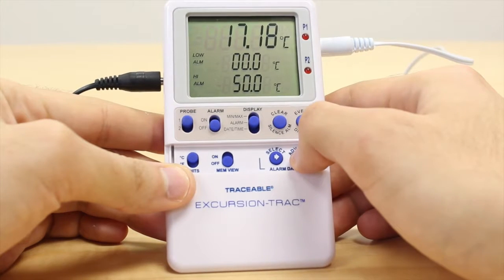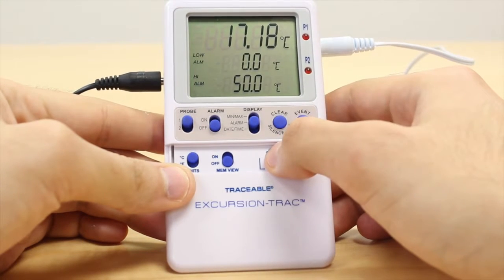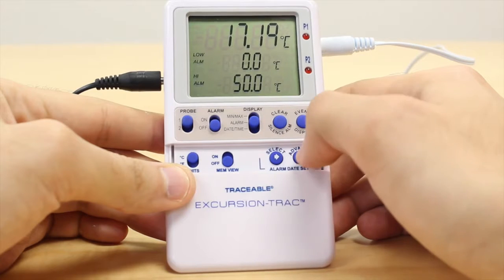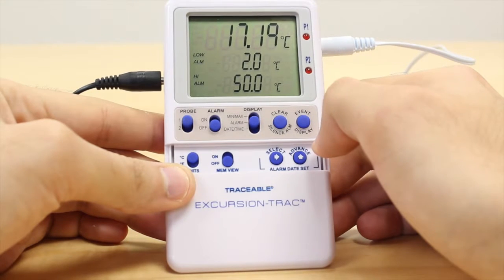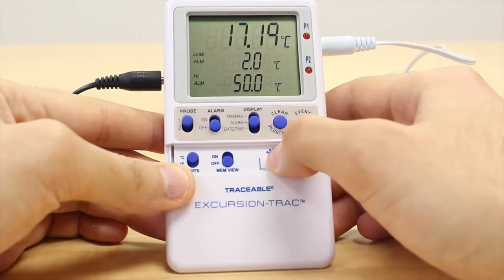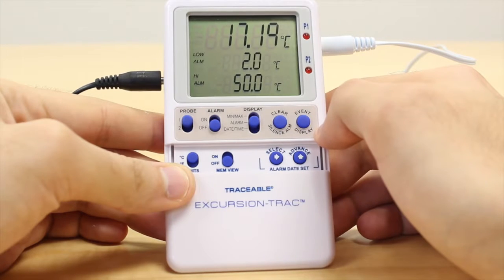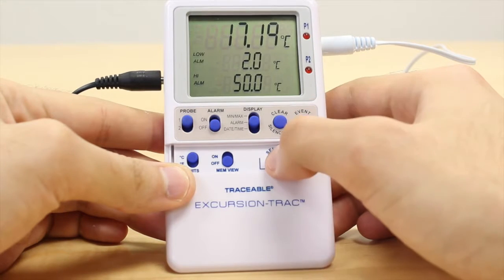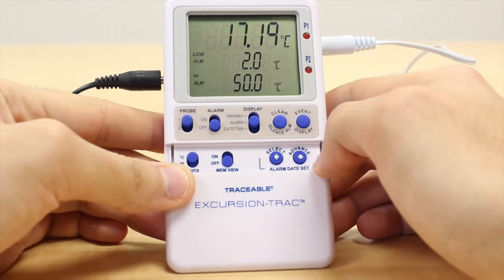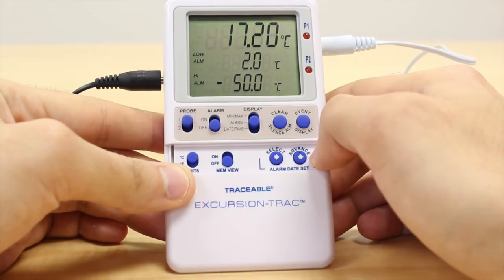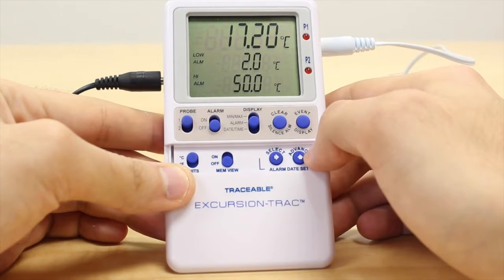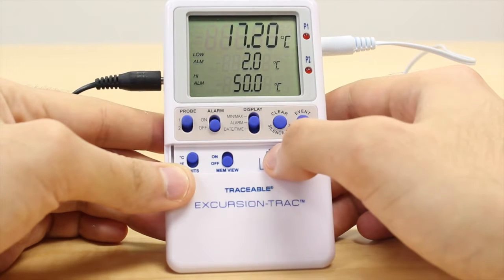Press the Select button once more to move on. Here is where I need a 2. Use the Advance button until you arrive at 2. Once set, press Select to move on. For this last digit on the low alarm row, we'll have to leave it 0. Press Select to move on to the next row. Now we're on the high alarm row, and currently on the negative value. It's currently set to positive, so press Select to move on to the first digit of the high alarm.